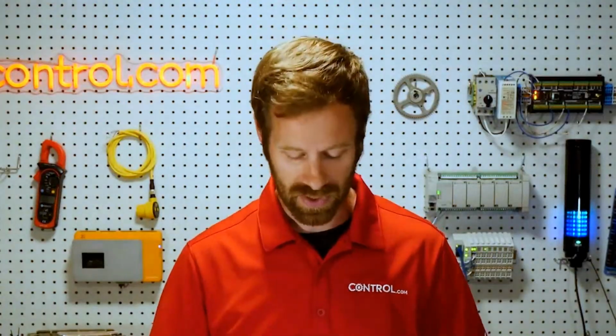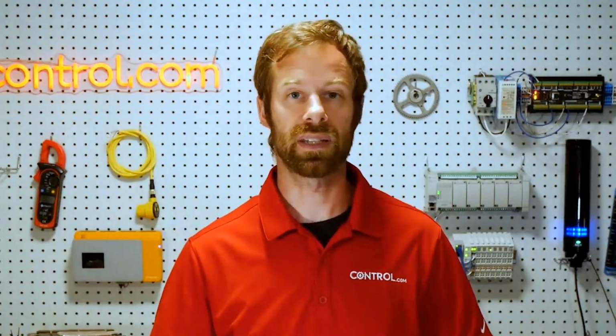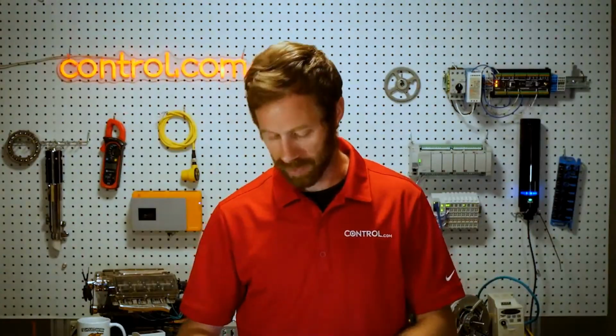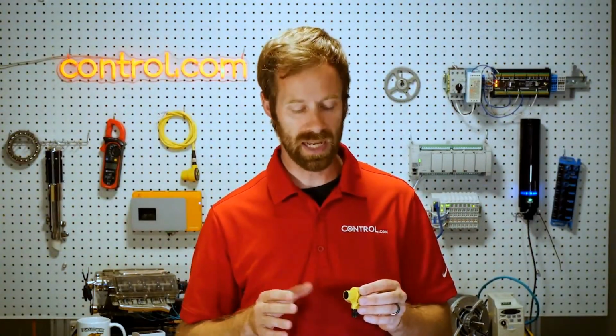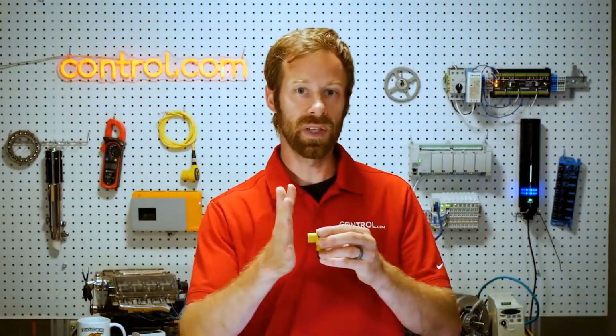IO-Link is that two-way communication where we can, from the controller or from the computer, send all of the set points, all the configuration information, lots of different details to the sensor, and we also have a record of everything that's going on all the time. Multiple set points, analog, discrete set points to be able to determine what configuration the sensor is currently set in. Like with these 3-wire sensors, once you set a position or teach a position to it, nobody really has any idea without testing what these positions are.